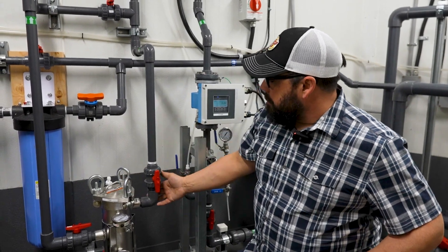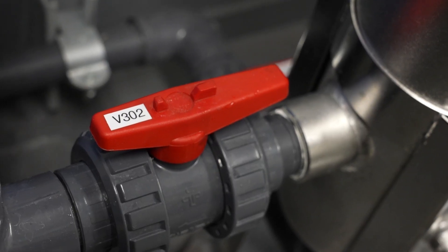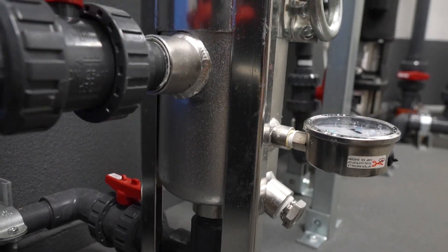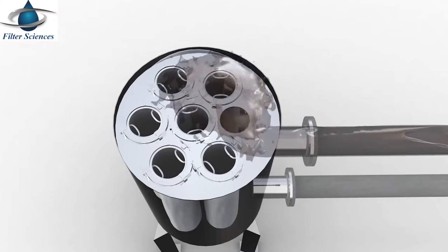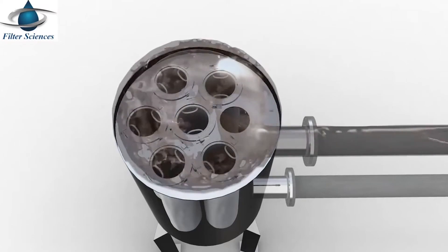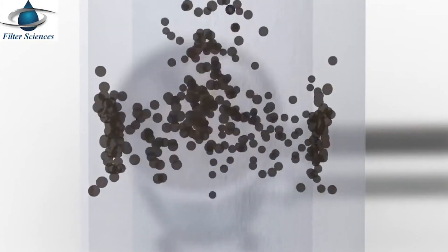You have your water coming in, then you have your water coming out. These bag filters are usually before any other treatment process because they will remove the larger particles—sand, rocks, sticks if you're from a surface water as well. So they'll remove any of the big particles so we don't plug up the rest of our system.